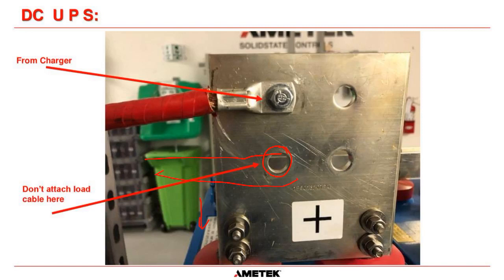You know, you can have your load cable coming in there and everything will be fine. But once again, if you have to replace this battery, then you are going to have to remove that terminal plate and replace it. And therefore, you're probably going to have to take a disconnect on your load circuits. So not a great design.